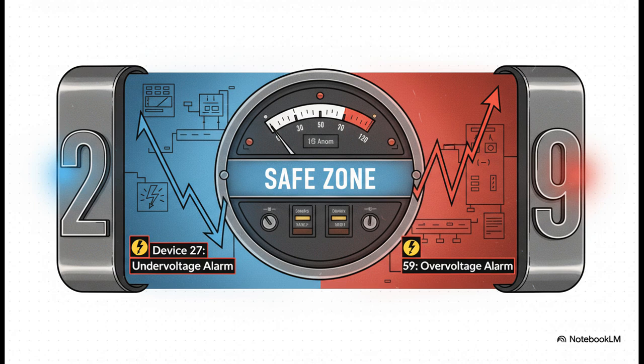Device 27 is the under-voltage relay. It keeps an eye out for when the voltage sags too low, think of a brownout, which can really damage sensitive equipment. And device 59 does the exact opposite. It protects against overvoltage, those dangerous spikes and surges that can literally fry your electronics. They keep the voltage in that safe Goldilocks zone.